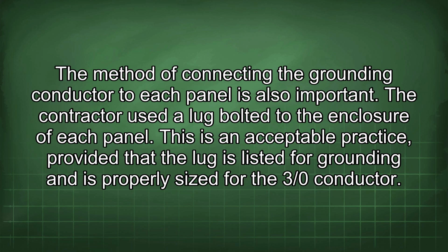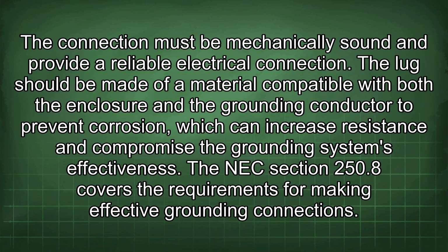The method of connecting the grounding conductor to each panel is also important. The contractor used a lug bolted to the enclosure of each panel. This is an acceptable practice, provided that the lug is listed for grounding and is properly sized for the 3/0 conductor. The connection must be mechanically sound and provide a reliable electrical connection. The lug should be made of a material compatible with both the enclosure and the grounding conductor to prevent corrosion, which can increase resistance and compromise the grounding system's effectiveness. The NEC section 250.8 covers the requirements for making effective grounding connections.